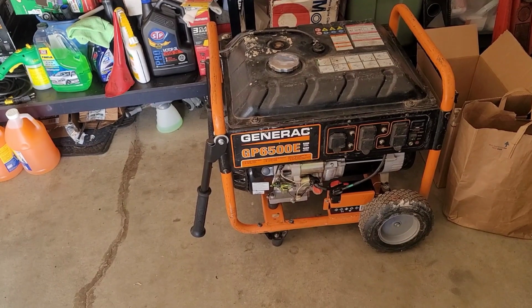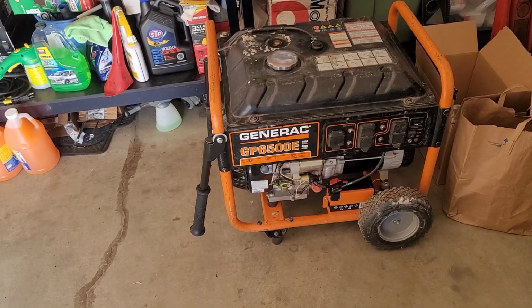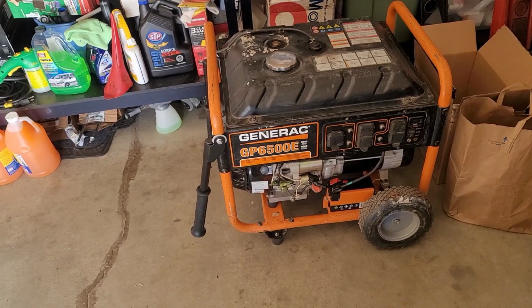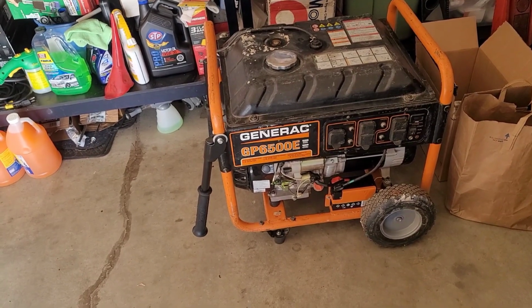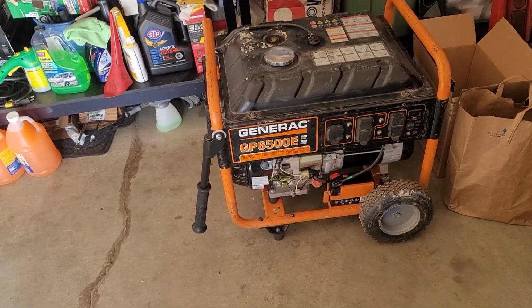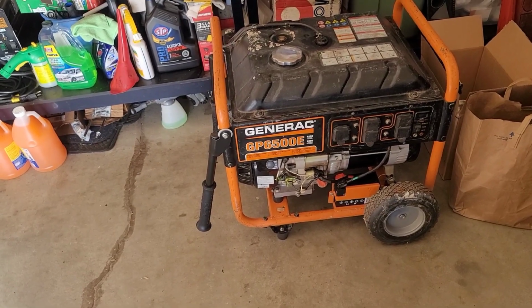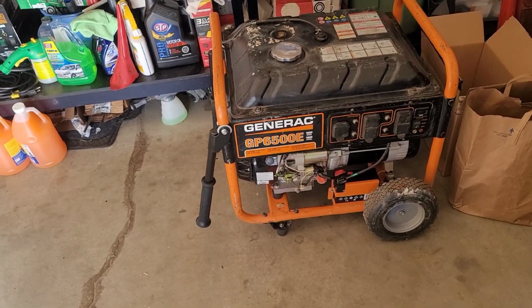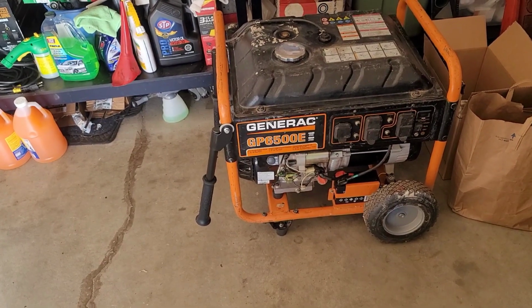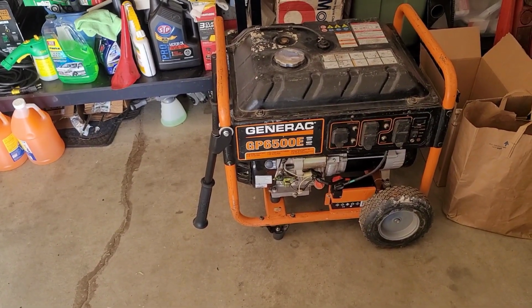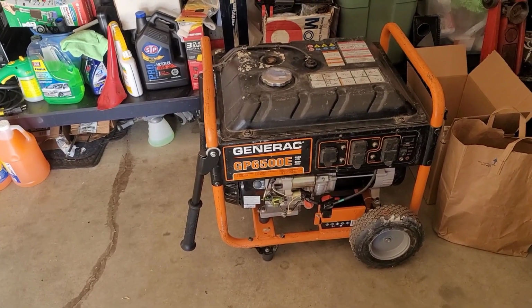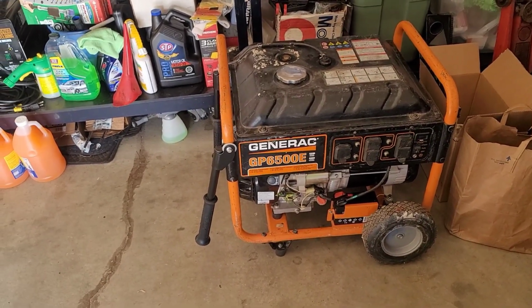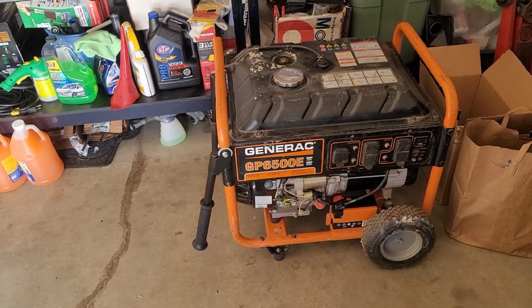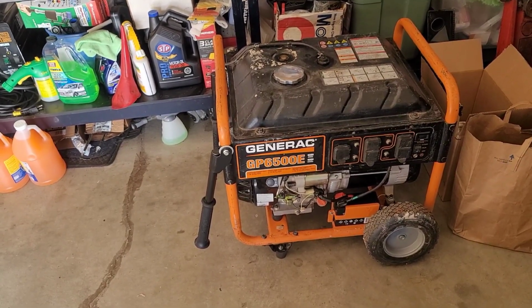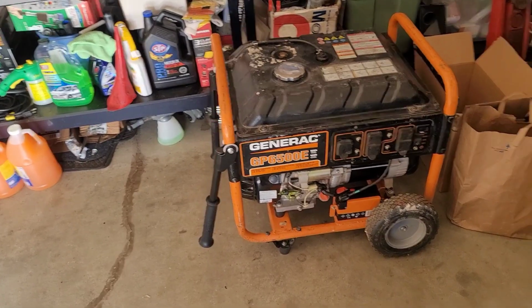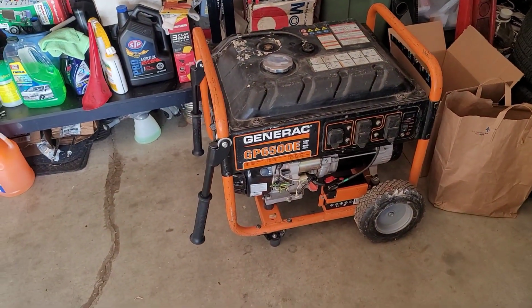Now, we did see on the total harmonic distortion meter that this generator, while it can have about 5% without a load, it jumps all the way up to about 17.5% under half a load, which would likely only go higher when you approach full load. That is typical and normal for a generator like this. I would not recommend using a generator like this for sensitive electronics like your computer, for example. There are some natural gas fired furnaces, even some fuel oil fired furnaces with the control boards that don't like dirty power that may have a problem running on a generator like this, so just be aware.